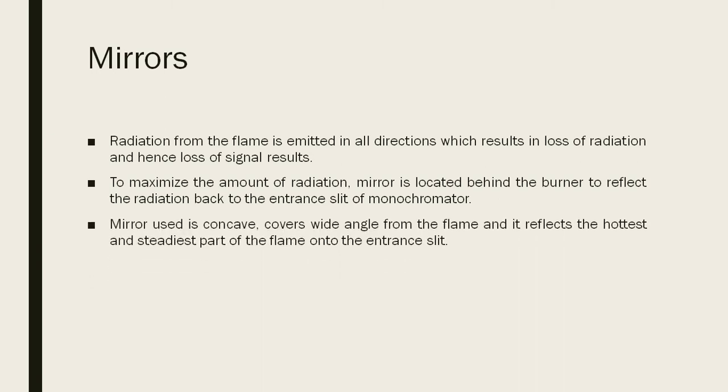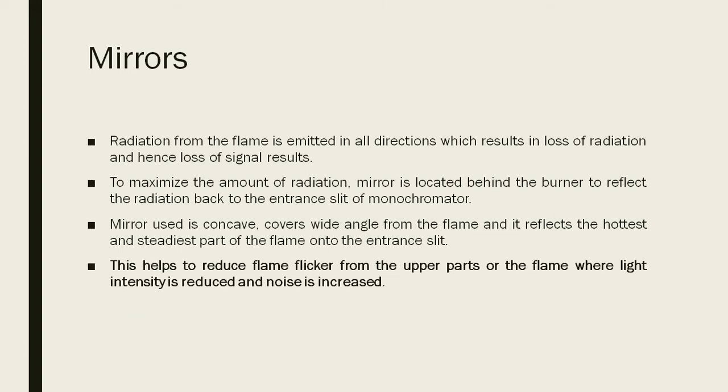The mirror used is concave. It covers a wide angle from the flame and it reflects the hottest and steadiest part of the flame onto the entrance slit. This will help to reduce the flame flicker from the upper parts of the flame where light intensity is reduced and noise is increased.